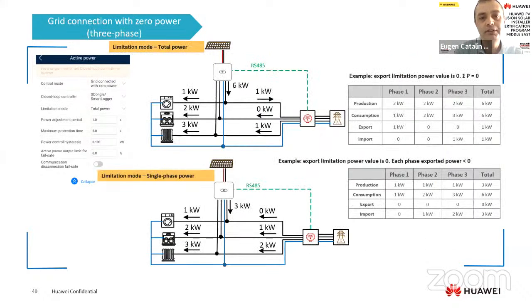Here we have zero in 3-phase. It's the same situation, but here we have 3-phase, and sometimes the phases are not balanced, and we'll have some phases export and some phases only import, but the total should be 0. And we have two situations here: total power settings with 0, and grid connected to 0 power. We have this limitation mode, total power.